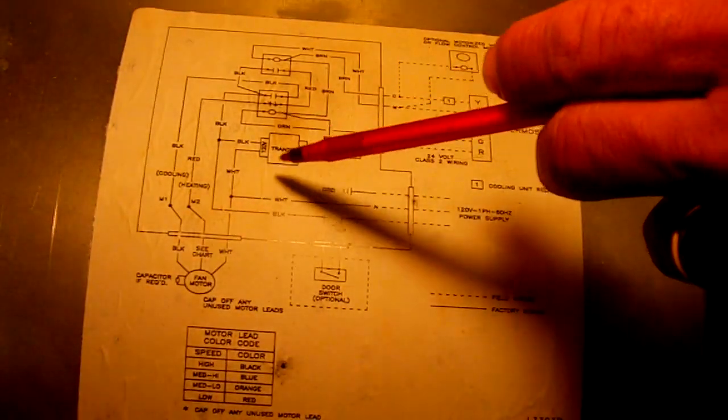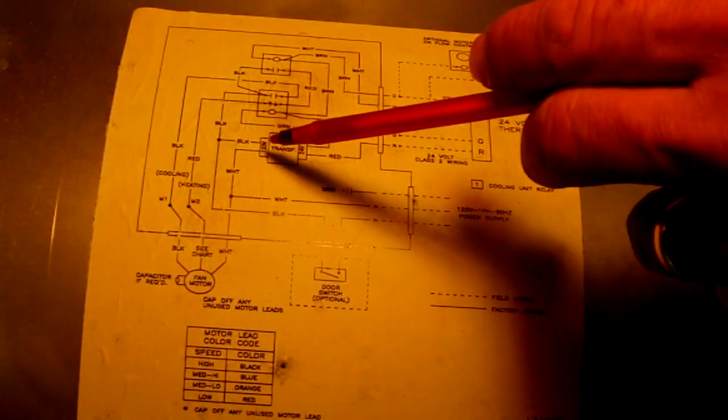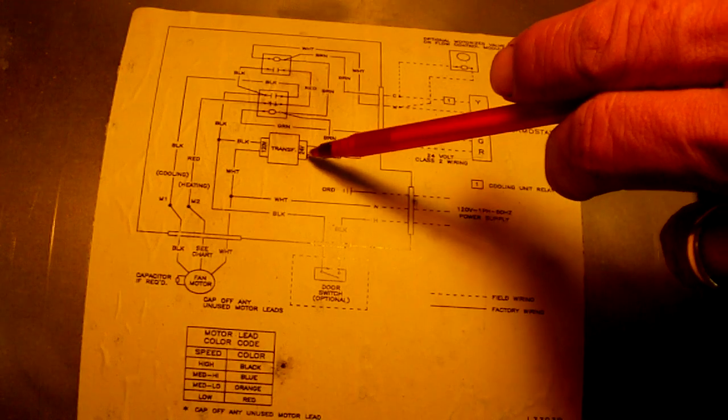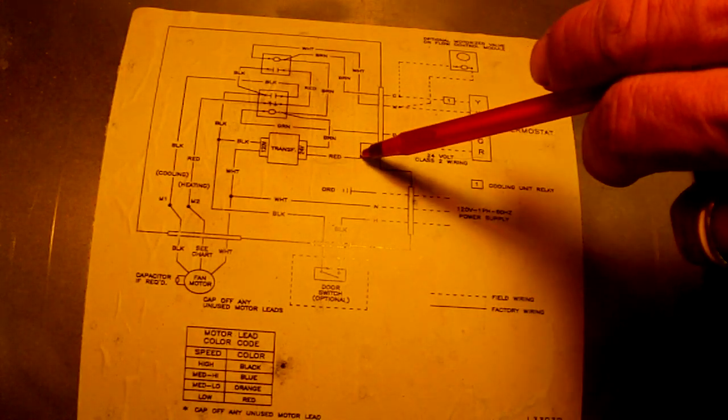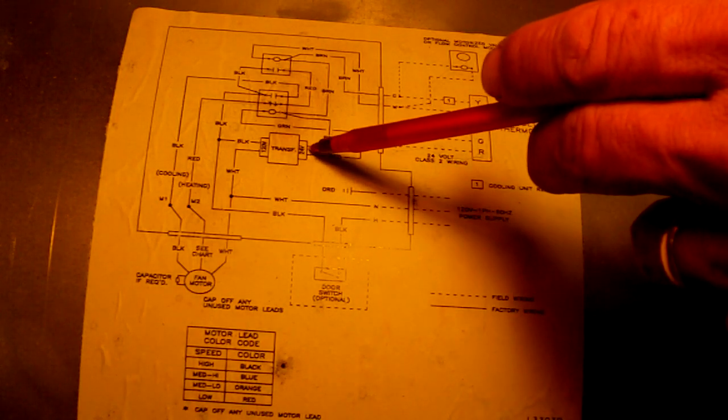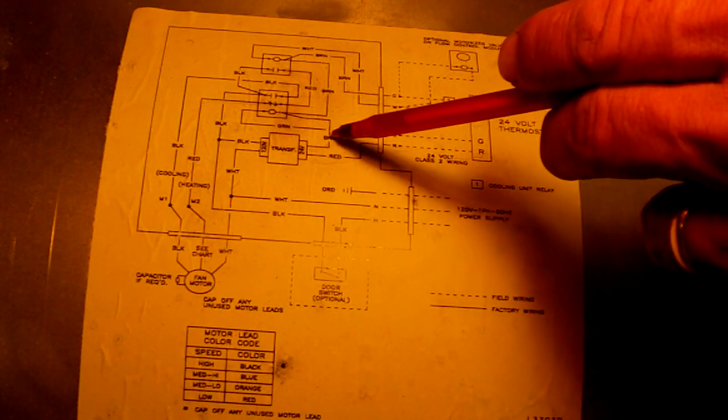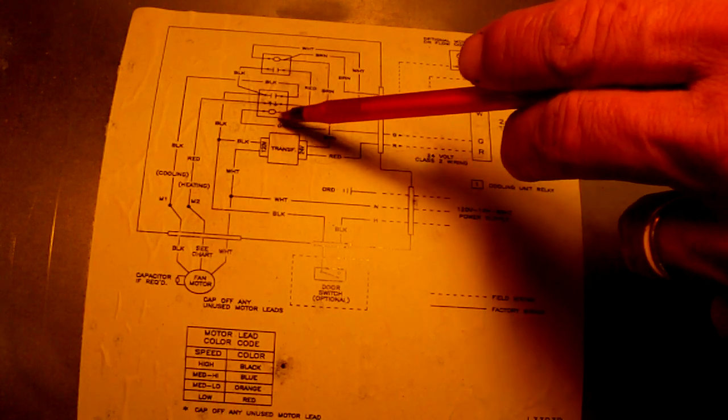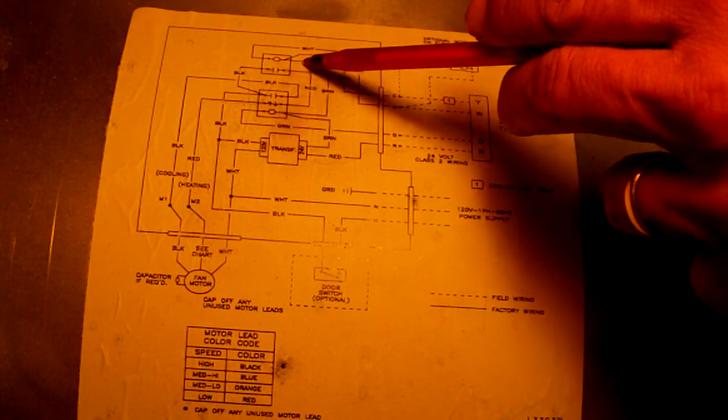On the other side, let's go back to the transformer. This is a step-down transformer, 24 volt. Red wire coming straight out to the thermostat block to R. The common wire goes to the relay, jumps out, and goes to the heat sequencer on this side.